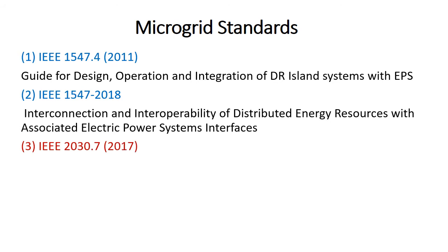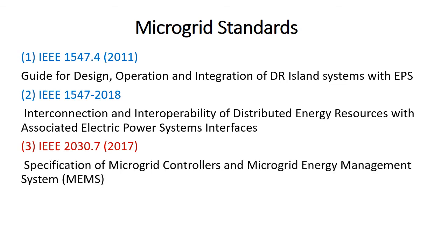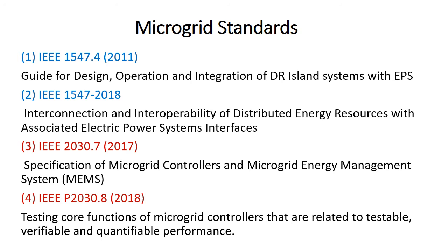The second group of standards is the IEEE 2030 series. IEEE 2030.7 covers the specification of microgrid controllers and microgrid energy management systems. The energy management system checks available stored energy and how much energy is being generated by various distributed energy resources, and controls them accordingly. IEEE 2030.8 addresses testing core functions for microgrid controllers related to testable, verifiable, and quantifiable performance.